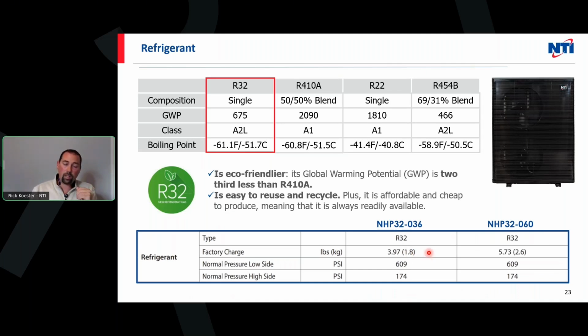Again, this is Mid-Atlantic. I would think this would be more popular up north in Canada, as well as the northern states, where we do see some applications where they want to put the outdoor unit in an indoor space, whether it be a garage, a parking garage, or some kind of mechanical space. One of the things I know with A2Ls that has been a challenge is understanding the volume of the space. The way some of the codes or standards have been written, anything less than 4 pounds of refrigerant typically does not need ventilation, leak detection, and stuff like that.